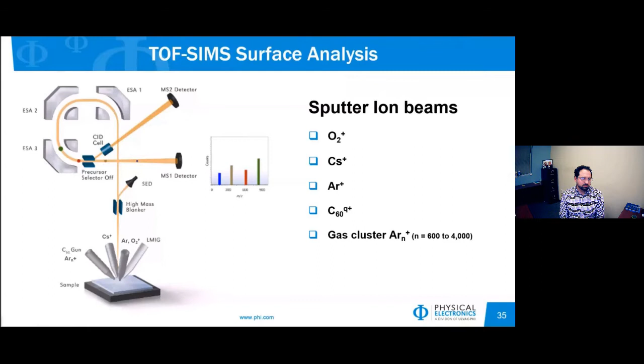And since it has multiple ion beams, you can use your LMIG or your primary ion beam to generate the spectrum, and then you can switch to a different ion beam to sputter to either enhance or remove the material at a faster rate. So with TOF-SIMS, you get the benefit of having a separate analysis and sputter beam. This is in contrast to dynamic SIMS, where your sputter beam is your analysis beam, so you don't have this choice of picking and choosing. As a result, you get a low impact sputtering event with high mass resolution. In the sputtering beams, as you go down in energy, it's harder and harder to focus due to the space charge effect.